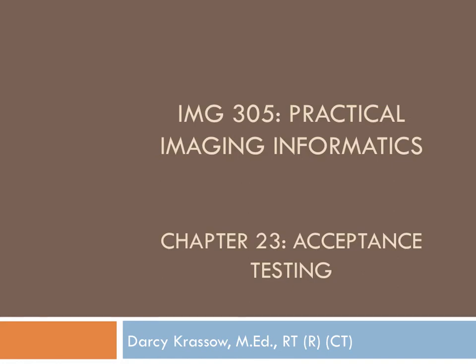Chapter 23, Acceptance Testing. Acceptance testing of PACS serves as an evaluation of its performance, identifying deficiencies, and the availability of the system. The acceptance testing is a technical evaluation of the system, and it demonstrates the clinical readiness for patient care. It also establishes the baseline for a facility's QC program for monitoring the PACS in the future. Acceptance testing is usually done by the radiologist, PACS administrator, biomed engineers, IT representatives, and/or radiology techs.